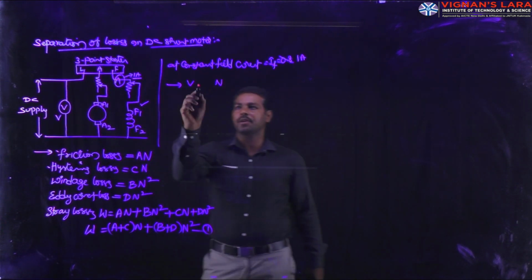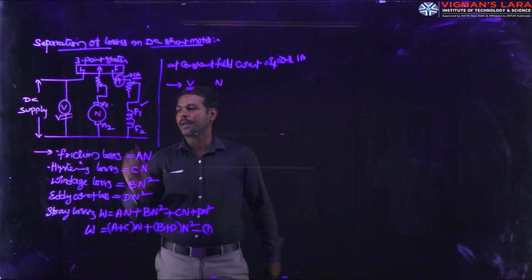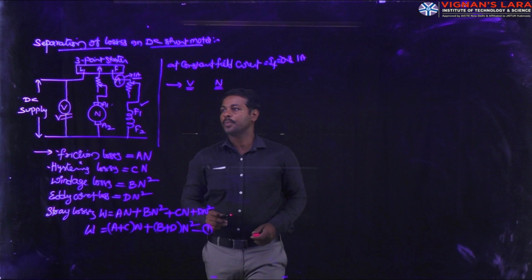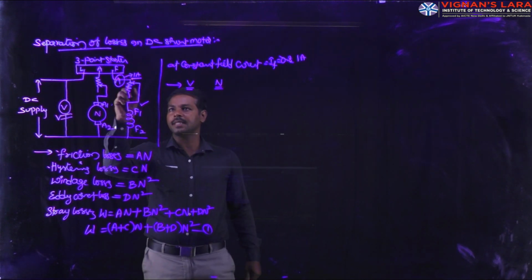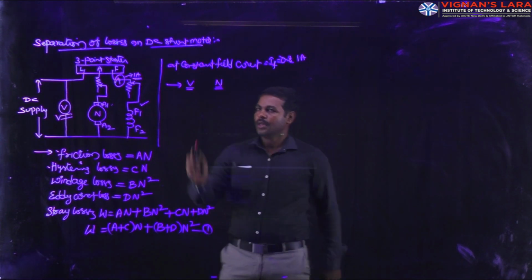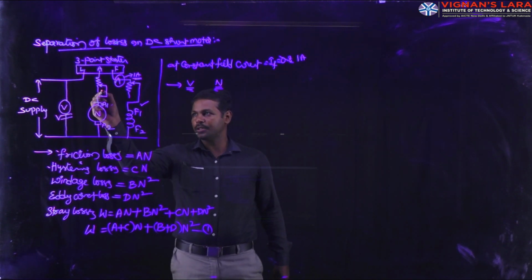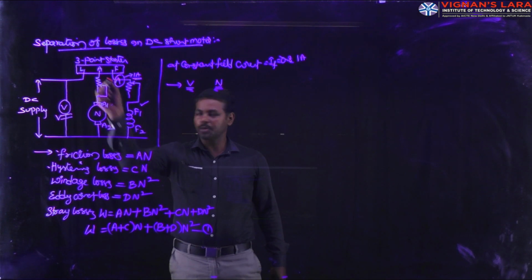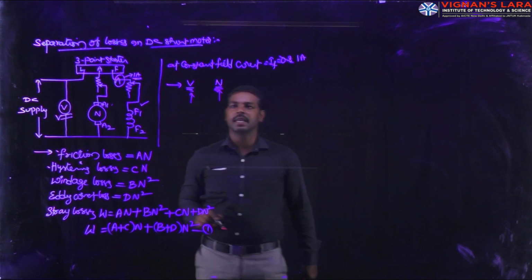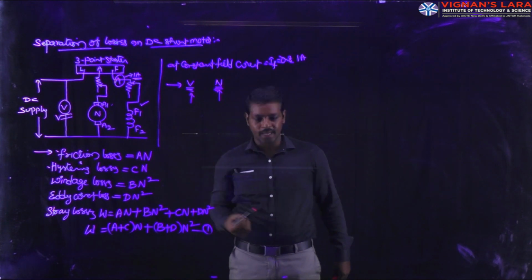As we vary the armature rheostat from maximum to minimum position, we note down the input voltage from the voltmeter and the corresponding speed of the armature. These two parameters must be noted with the field current kept constant at 1 ampere. Whenever the rheostat is decreased from maximum to minimum position, voltage increases and the speed also increases. Based on these two values, we can draw the characteristics.